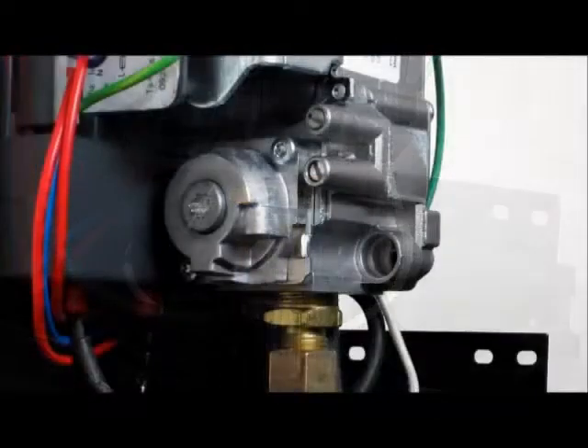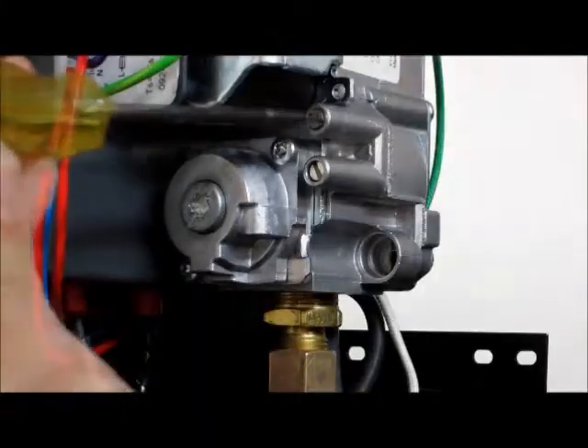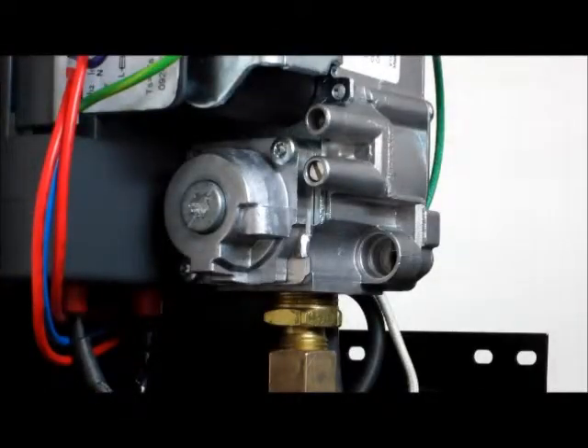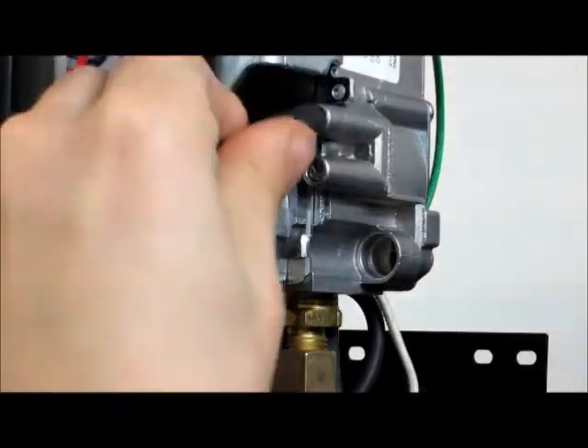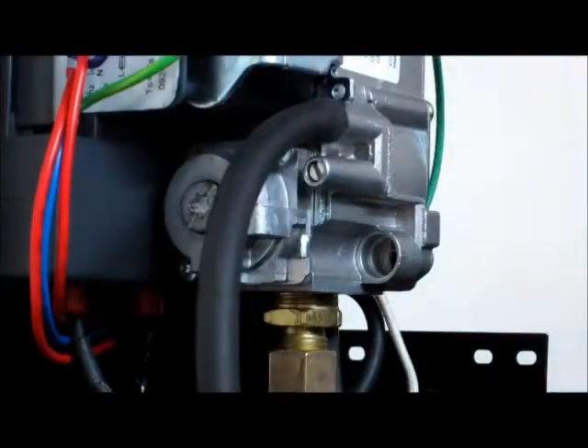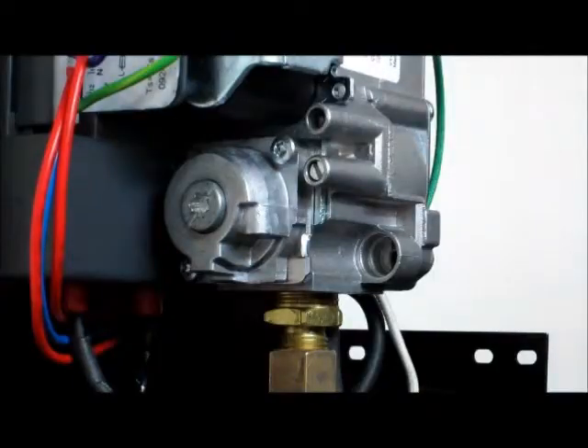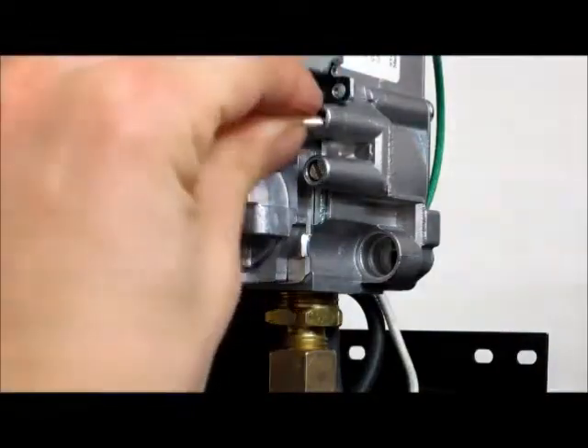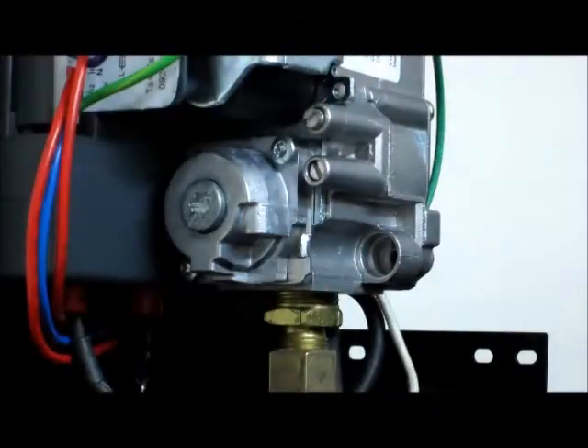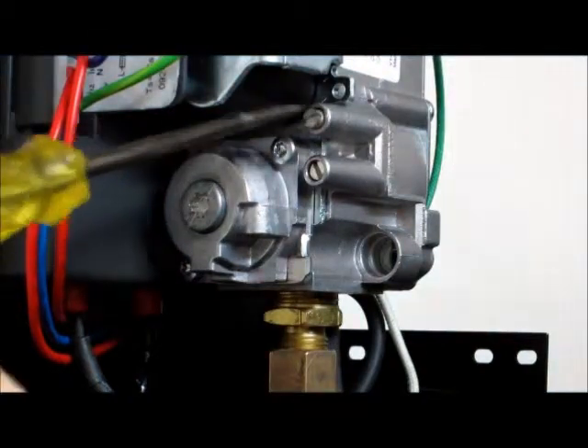If the hose is in good order, we must then ensure gas flow is reaching the unit. By connecting a manometer to the inlet pressure test point, verify the inlet pressure is sufficient, but no higher than 50 millibar as stipulated in the instruction manual. If no pressure is registered at the inlet, gas flow is not reaching the unit and must be restored before re-attempting to light the heater.